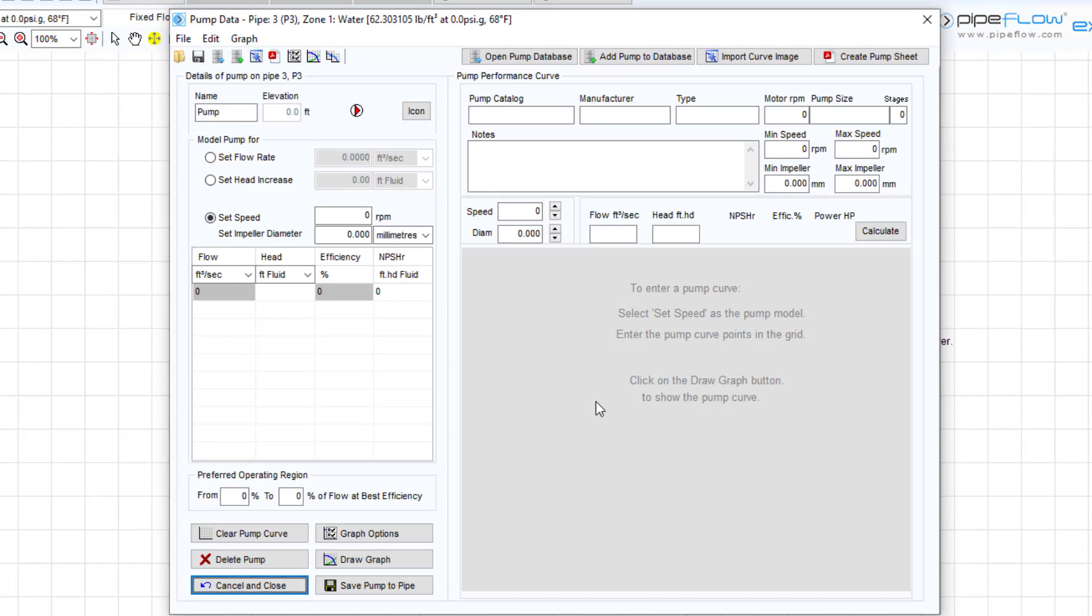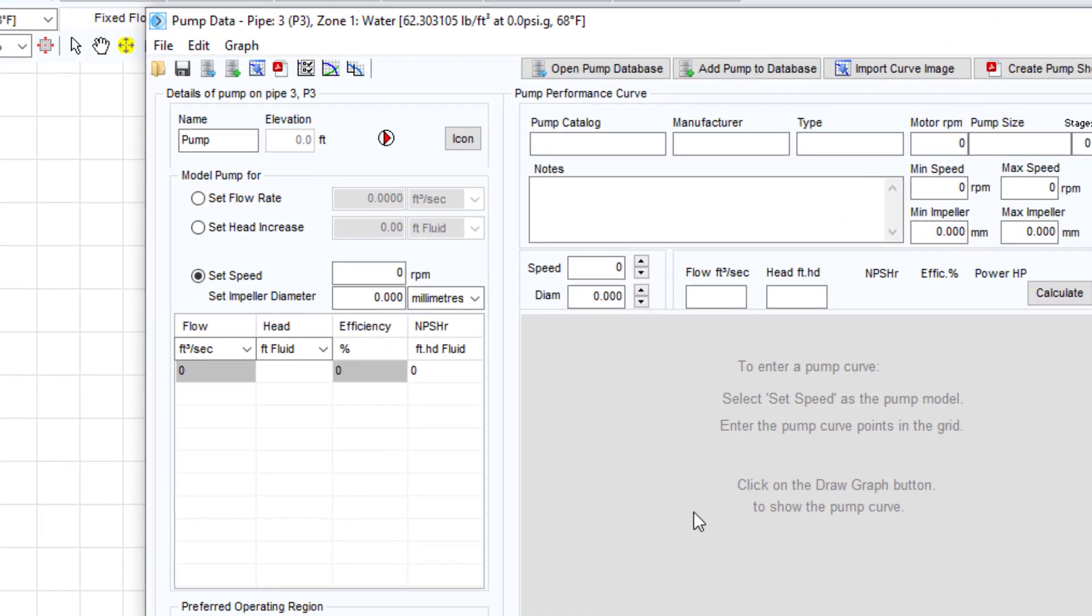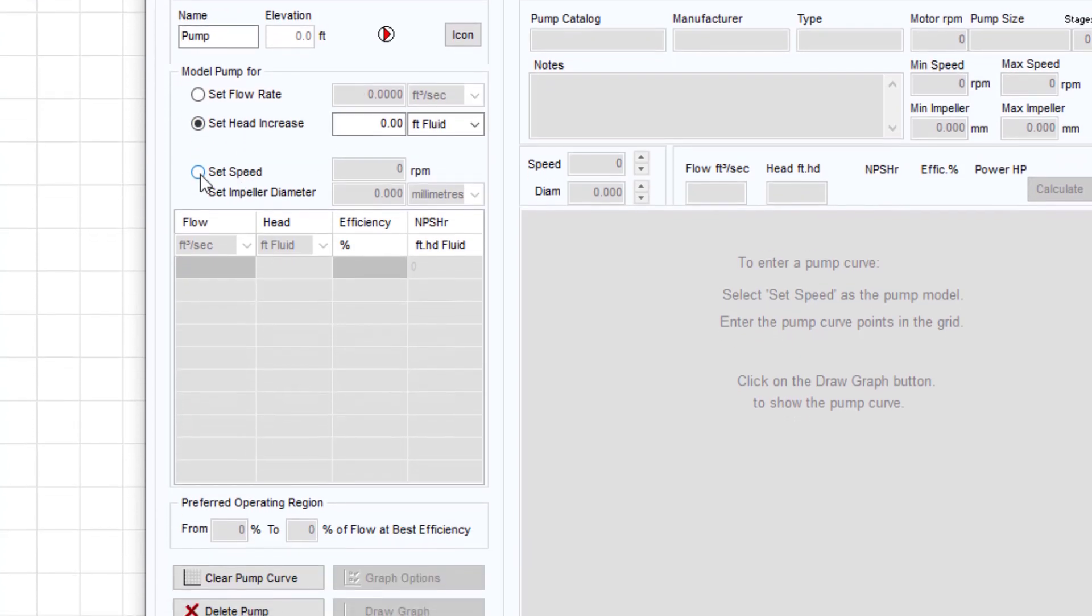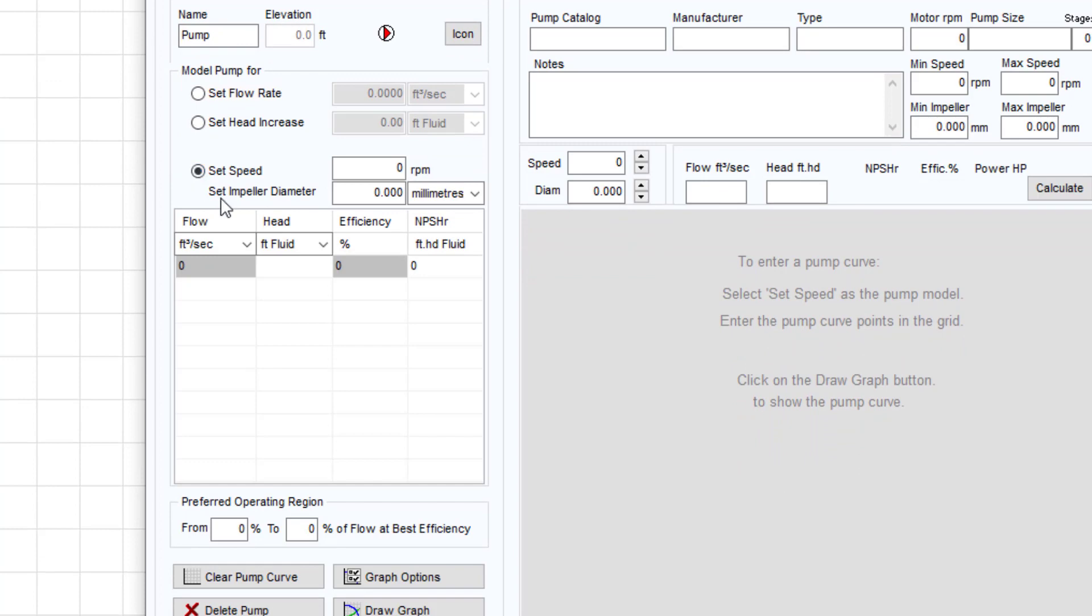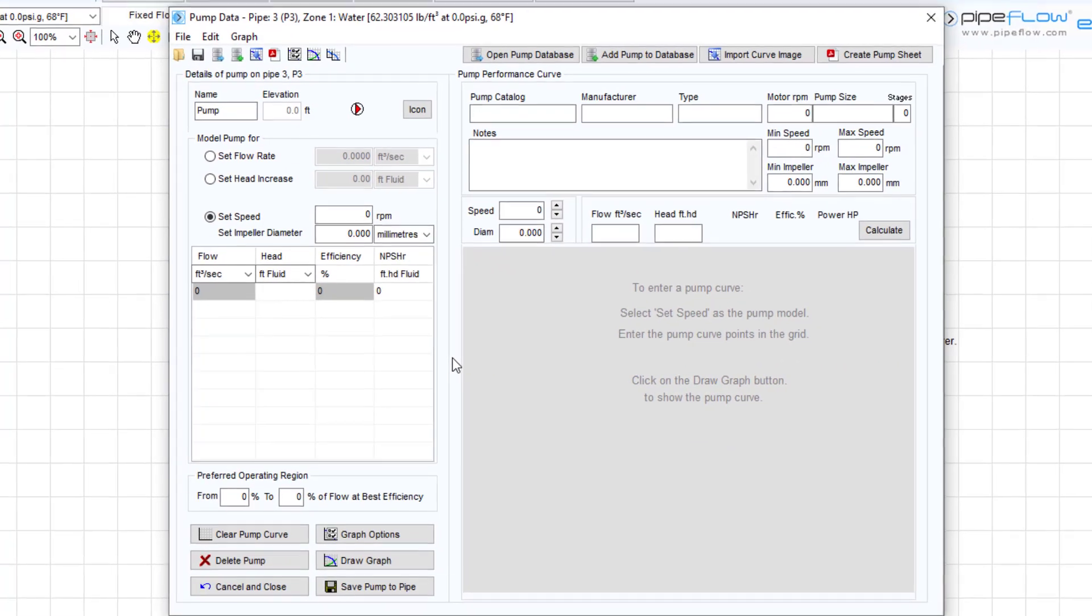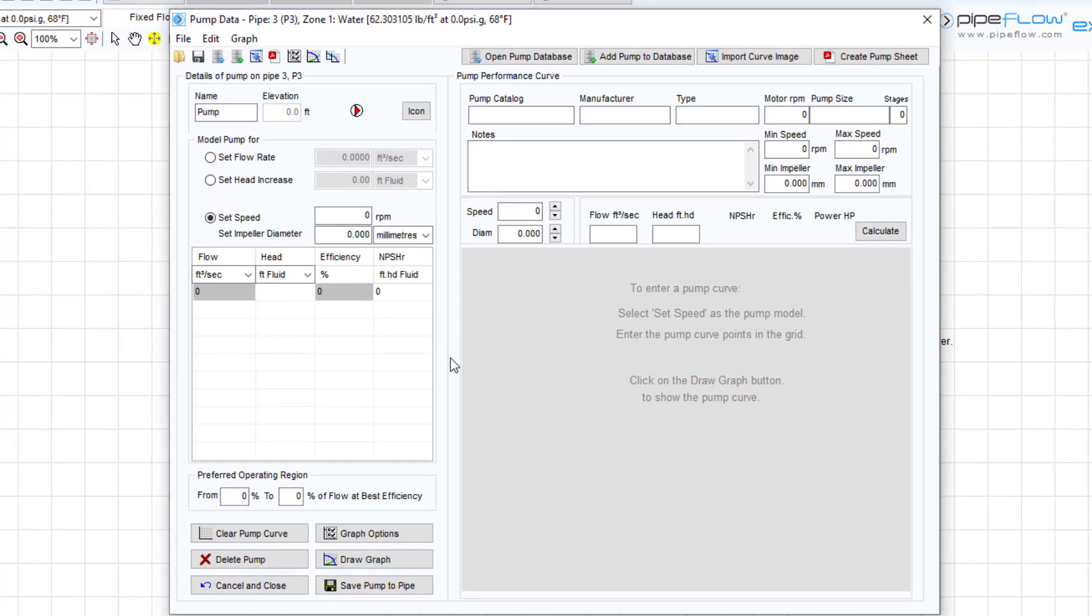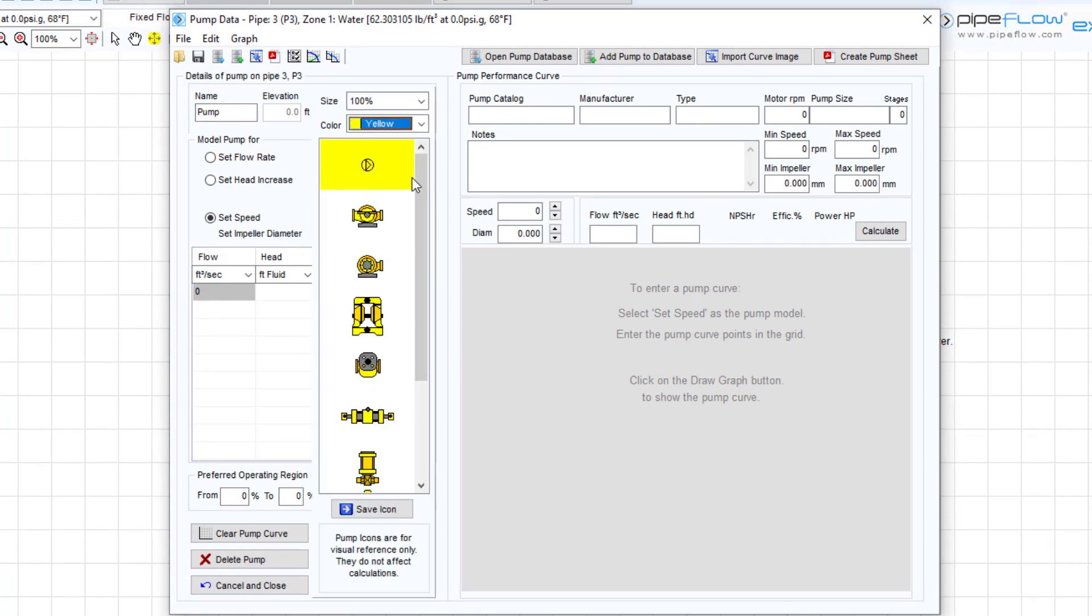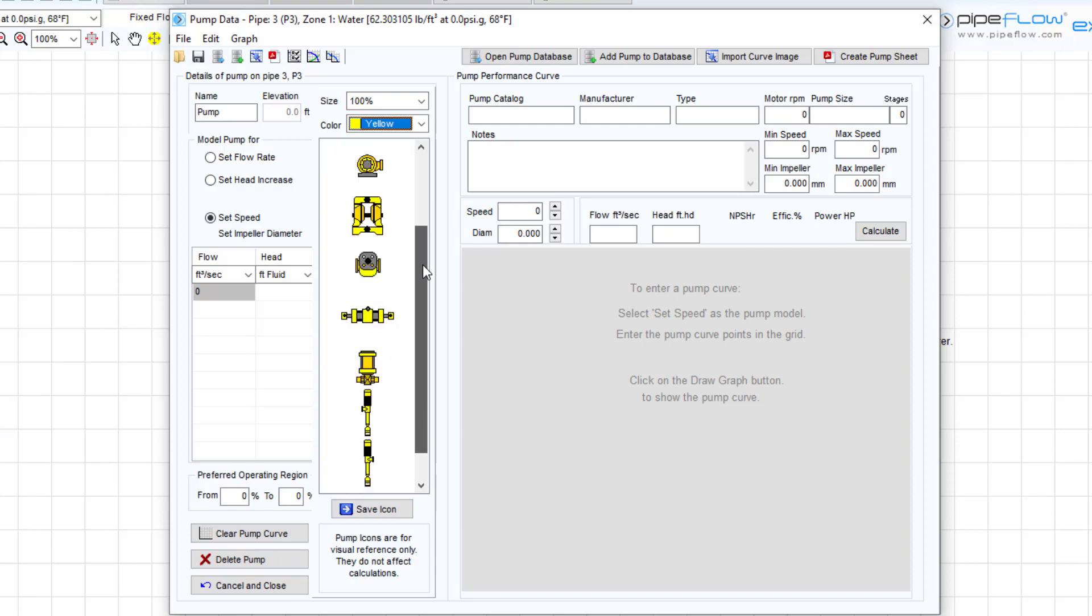To get started there are three main pump modelling methods. You can define a fixed flow rate, a fixed head increase, or specify a flow versus pressure loss performance curve for a set speed. An appropriate name, image, colour and scale can be selected to visually represent your pump on the drawing. This has no bearing on the mathematical calculation.